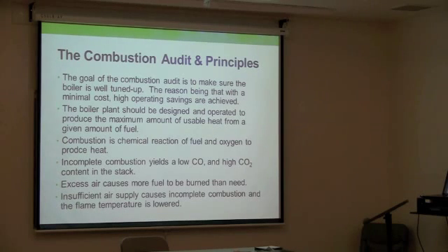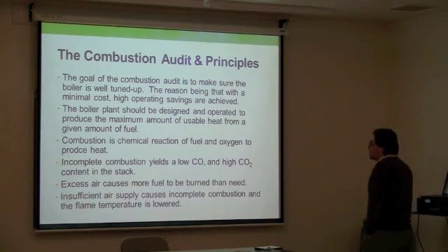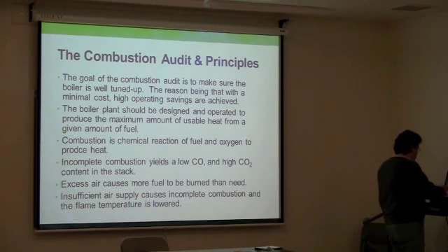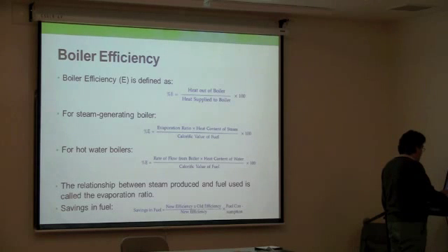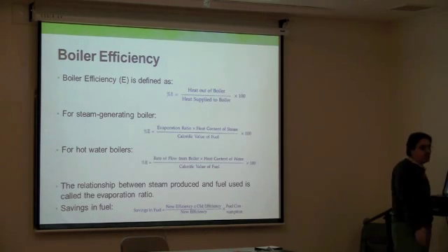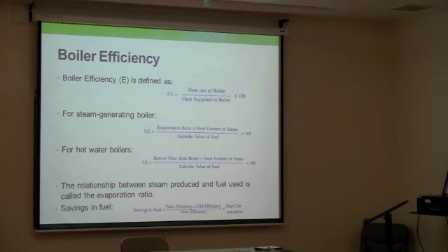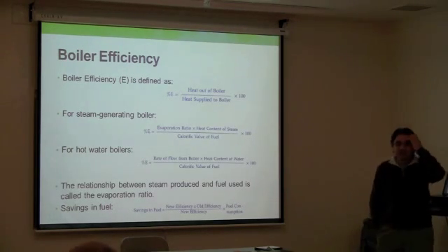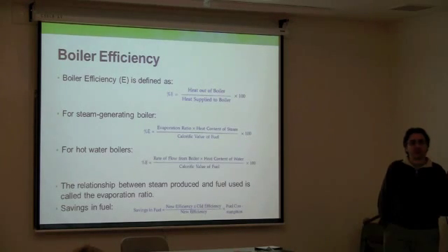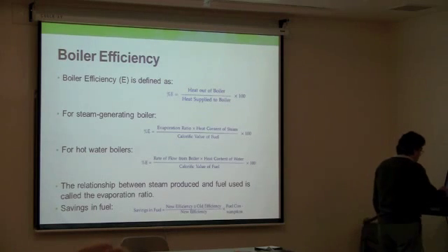So making decisions like that must be backed up by analytical calculation, and you can easily calculate all of those things, the level of the CO2 in the flue gas, and all of those things. You're dealing with boilers. Every boiler has an efficiency, right? Usually you cannot change the efficiency of the boiler. That is by design. But you can control the leakage out of the boiler. You can make sure the boiler controllers are clean and working properly. You can make sure of some of the operation of the boiler. You can make sure the burner is clean. You can make sure the air-fuel ratio is correct, which is the most important parameter in the boiler operation.